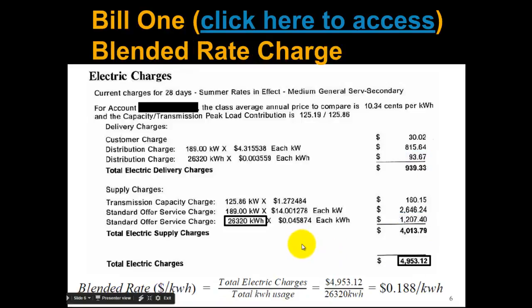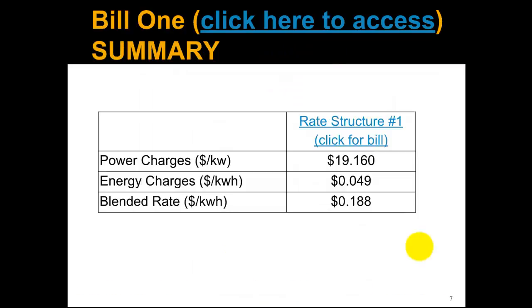Now let's look at another way to calculate this — and hopefully I'll convince you by the end of this video, this is not the way you want to do it. We really do not want to calculate electricity charges this way, but some energy auditing firms and some solar firms still do it this way. If we just take the total kilowatt hours and the total charges and divide the charges by the kilowatt hours, we get almost 19 cents per kilowatt hour — that's sometimes called a blended rate. Bill number one has very high power charges, relatively low energy charges, and the blended rate is relatively high as well.